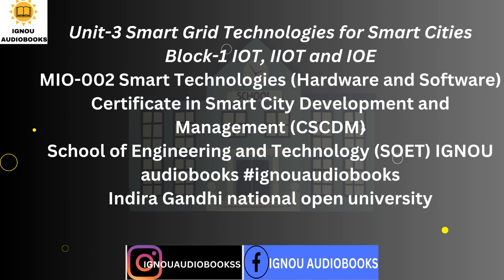automatic feeder switching. Flicker is defined as impression of unsteadiness of visual sensation induced by a light stimulus whose luminance or spectral distribution fluctuates with time. It can be eliminated by proper designing the power system to handle load variations, using rapid response voltage regulators, static var compensators, or fast response reactive compensation using inverter reactive power.